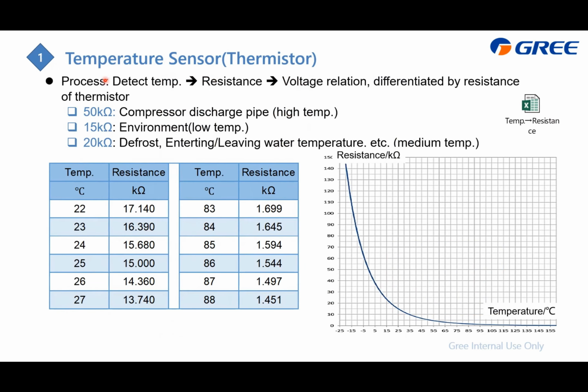First is the temperature sensor. We also call it thermistor. Actually, the temperature sensor is just a resistance, but its value is very sensitive to the temperature, which means if the temperature changes, the resistance value also changes. Then for the PCB, we always use the voltage to check it, which means the voltage also changes. Then the PCB can get the temperature information, and based on that, the system will change the component parameter.